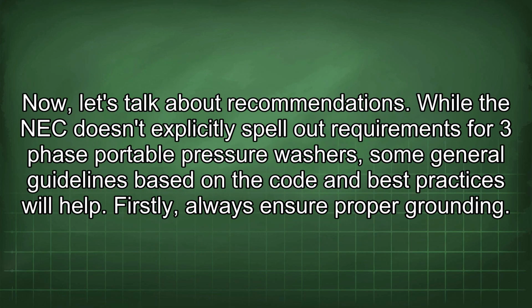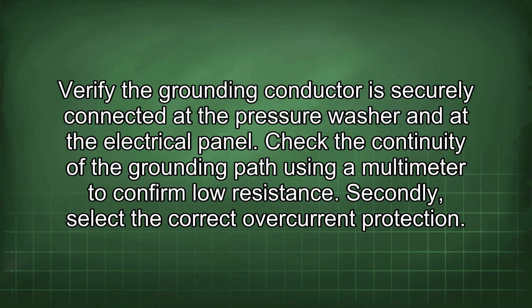Now, let's talk about recommendations. While the NEC doesn't explicitly spell out requirements for three-phase portable pressure washers, some general guidelines based on the code and best practices will help. Firstly, always ensure proper grounding. Verify the grounding conductor is securely connected at the pressure washer and at the electrical panel. Check the continuity of the grounding path using a multimeter to confirm low resistance.